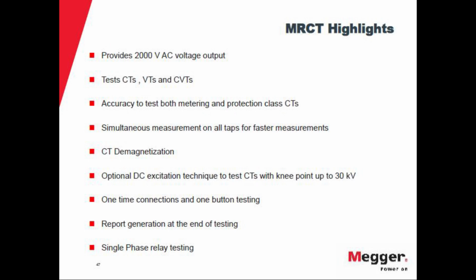To perform the test, the instrument can provide up to 2,000 volts, so it can saturate the core of the CT. In addition to testing CTs, it can also test VTs, like voltage transformers, or capacitive voltage transformers. And we have accuracy for both metering and protection class. Protection class CTs don't need to be that accurate. The standard specification is that they have to be 10% accurate when the current is 20 times the nominal current. So it's not a high accuracy, but on the metering side, they have to be very accurate. They have to be 0.3 or 0.2 or 0.1% accurate. And for that, you need a very accurate instrument to perform the measurement. So with one single instrument, we have the capability to test both types of CTs.